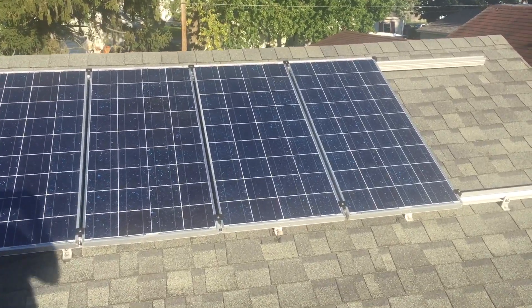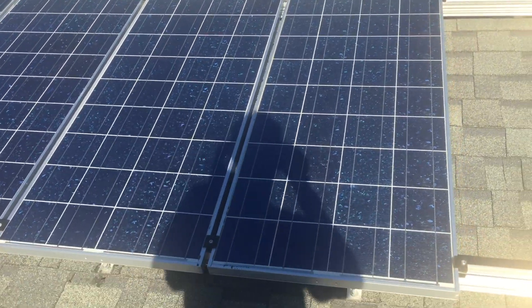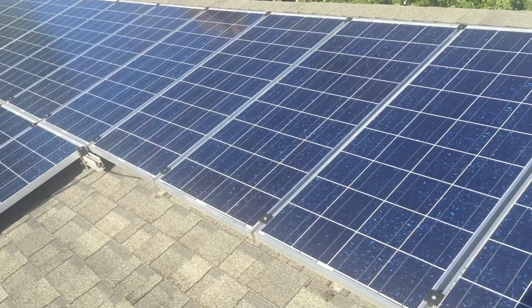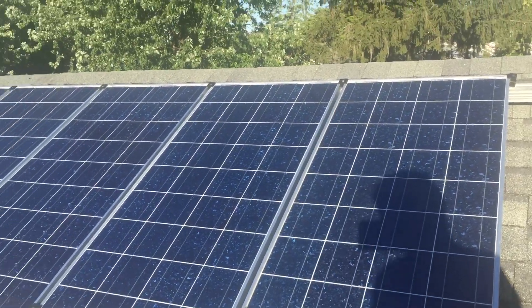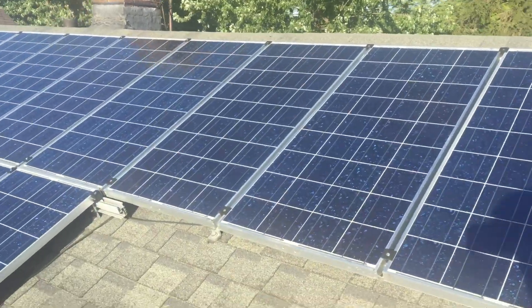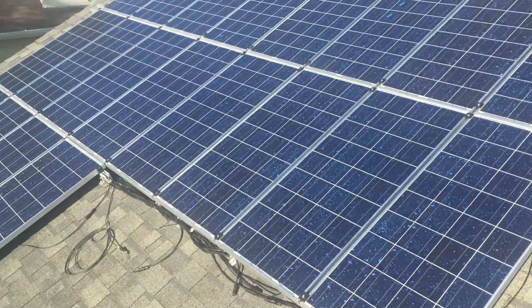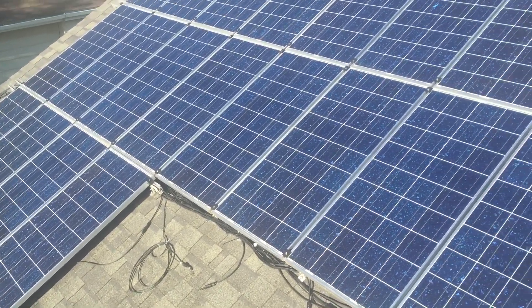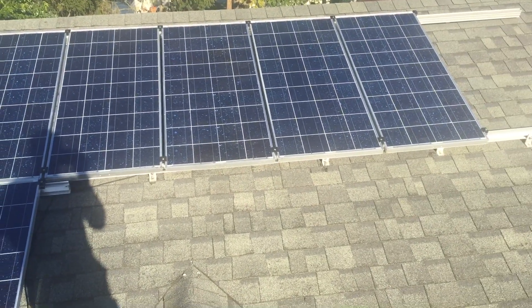Right here you see 24 120-watt panels. Probably should have went with 230s, but I got a good deal on the surplus of these — I got about 40 of them, so this is what we're going to go with. Each one of these are 120 watts. They're 12-volt panels. These are all run at 48 volts, 4 per set in series. So there are 6 sets here of 4 in the array.